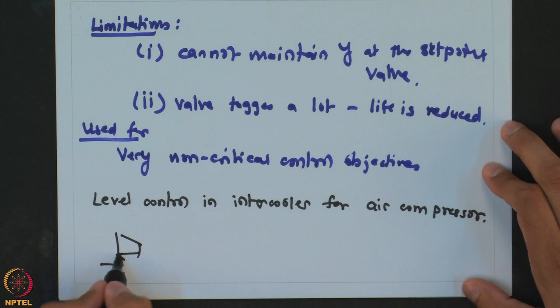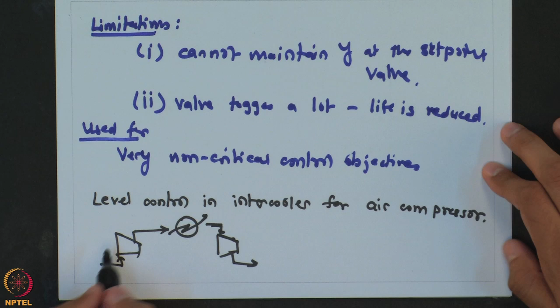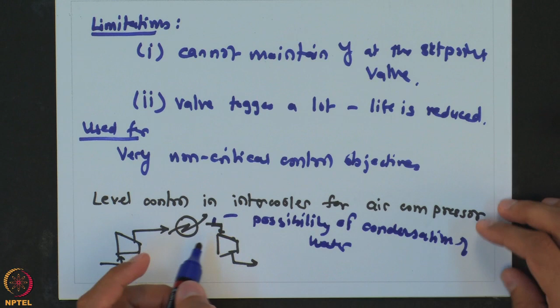So, what happens is whenever you are trying to compress air from ambient conditions to some higher value, you would typically go with multi stage compressors, and as the compression of air is going to increase its temperature, in order to maintain the efficiency of compression, you have to cool that air stream before it enters the next compressor stage. As we are dealing with air, air also has a capacity to hold moisture, and as you compress the air and reduce the temperature after this cooler, there is a possibility of condensation of water at that point. And if we have this two phase mixture of air and water which goes into the compressor, again that is very detrimental to the compressor blades.